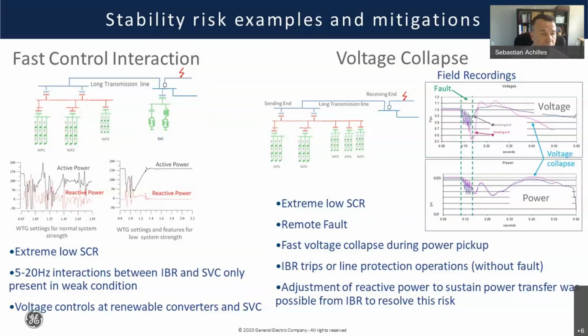And you can see that there is sort of an oscillatory behavior. There's a fault and clear, and the system didn't recover. If you look at the details of the wiggles, there is a noticeable oscillation in reactive power around 20 hertz. If you look at the SVC that is not shown in this plot, you will find a similar oscillation. So there is a clear oscillation of reactive power between the SVC and the wind turbines.